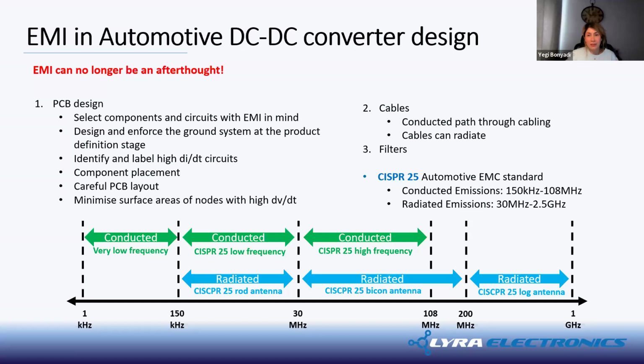Identify your di by dt and dv by dt circuits and nodes, and minimize the surface areas for these components. Also be really careful about your PCB layout. If you've got cables, bear in mind that cables can radiate, and the conductor path through cabling is quite important. Also, knowing how to design filters to be effective in the frequency range that you're interested in is quite important. As I mentioned, CISPR 25 is what we had to test to, and you can see on the diagram below that the conducted and radiated emission tests have different frequency ranges. For conducted emission tests, the range is from 150 kilohertz all the way to 108 megahertz, and radiated emission tests go from 30 megahertz all the way to 2.5 gigahertz.